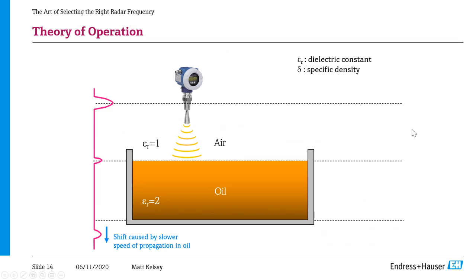So go to the next slide and look at what signals look like in a lower dielectric, something like an oil-based product. For a radar, you have that same signal launch, it travels down. Now you see you get a much smaller reflection off the surface of that oil because of the lower dielectric. And then actually some of that energy is reflected, but much of it actually continues to travel down through the oil. And you see at the bottom left of the screen another peak.